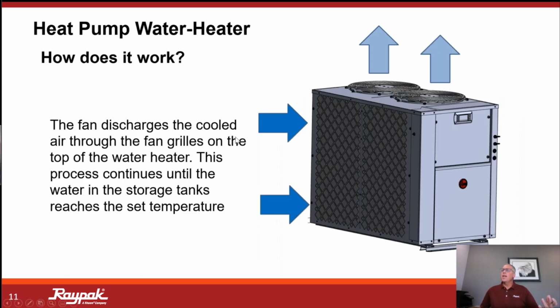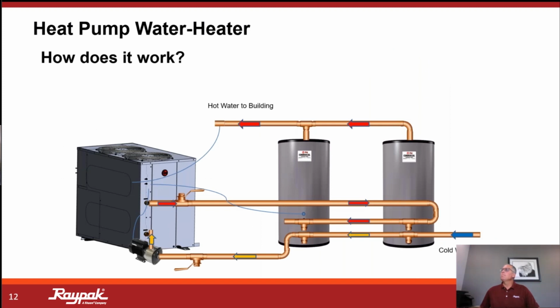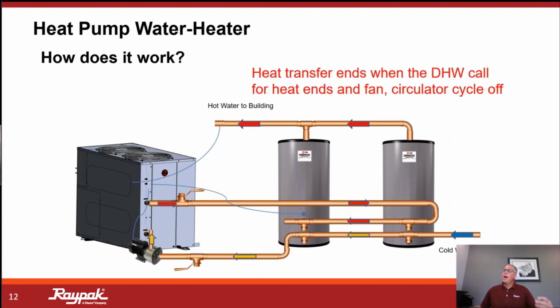Okay, and then as we said again, the fan discharges the cool air after we extract that heat from it. So in principle, it's very, very simple in terms of refrigerant flow path, the water flow path, and the air flow path. All of those things in harmony will result in a stored water temperature that will give us usable domestic water. Again, just another example here. It will end when this tank satisfies and we reach that set point. And then we'll go into essentially a post-purge with the pump, very similar to what we already know. So again, nothing exotic there.